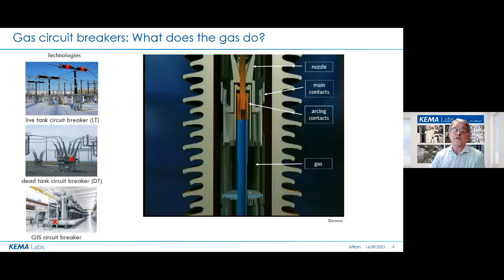Then what is quite important, some contacts are involved, and we have 2 types of contacts in gas circuit breakers. The main contacts make sure that the normal conducting function of the breaker is with low losses, whereas the arcing contacts have to deal with the tremendous heat of the arc. Well, then, of course, quite important, and we will also come back to that, is the nozzle of the device, which has the function to let the extinction gas flow around the arc.